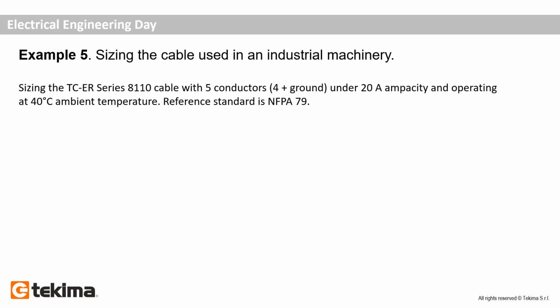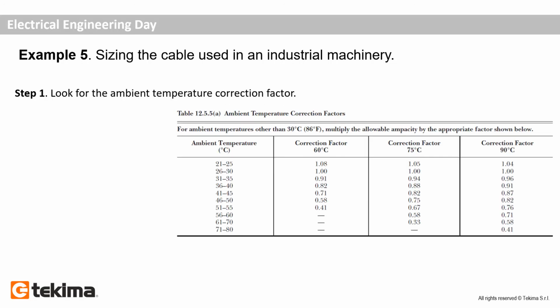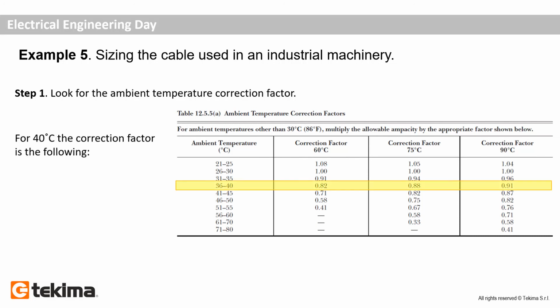In example number 5, we will size again a tri-cable exposed run series 8110 made of 5 conductors operating at 20 amperes and 40 degrees Celsius ambient temperature. The standard reference is the NFPA 79 industrial machinery. The first step is to understand what is the rating factor for the ambient temperature. We are working at 40 degrees and the tri-cable that we have to size has a temperature rating of 90 degrees, which means that the rating factor for the ambient temperature in this case will be 0.91.